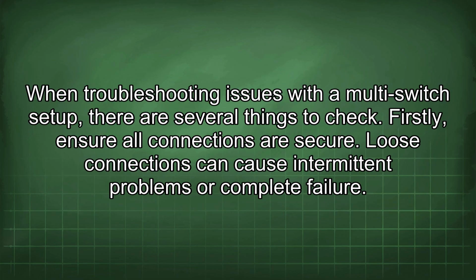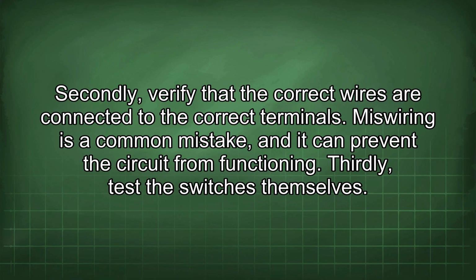When troubleshooting issues with a multi-switch setup, there are several things to check. Firstly, ensure all connections are secure. Loose connections can cause intermittent problems or complete failure. Secondly, verify that the correct wires are connected to the correct terminals. Miswiring is a common mistake, and it can prevent the circuit from functioning.